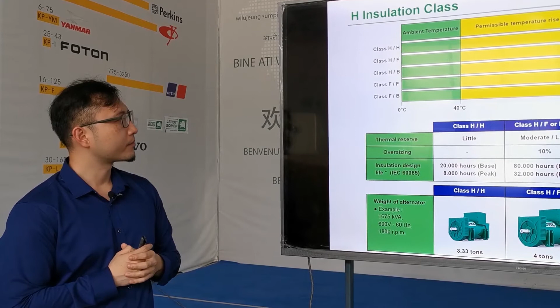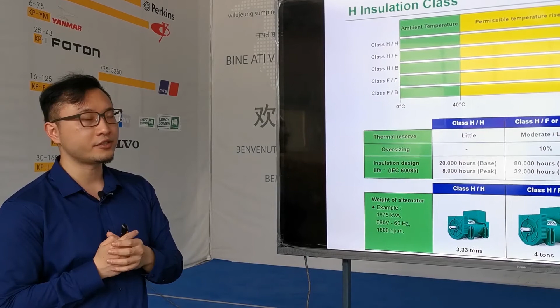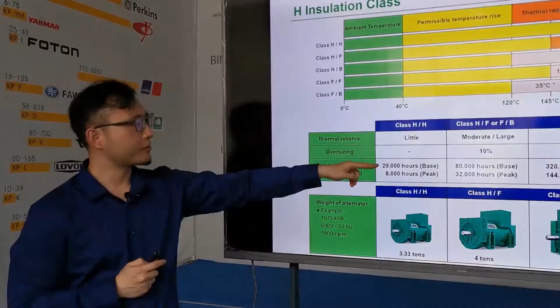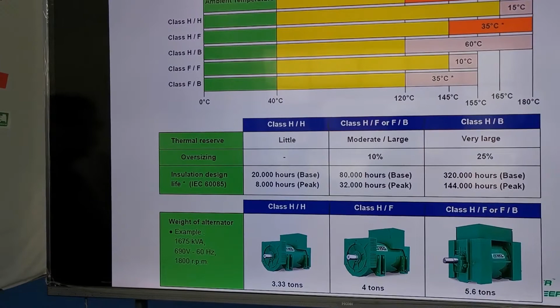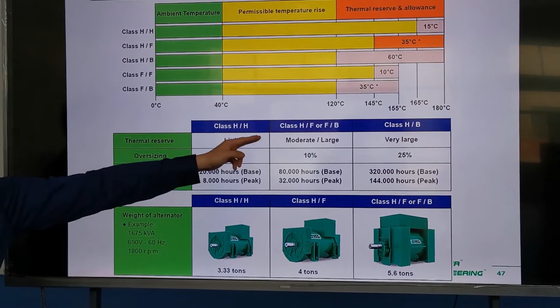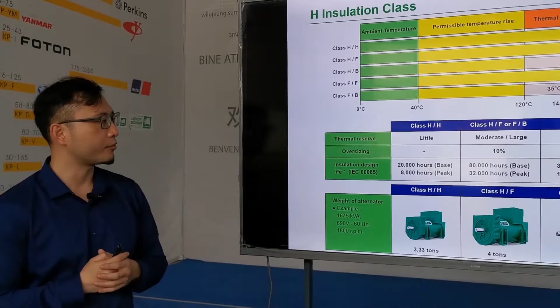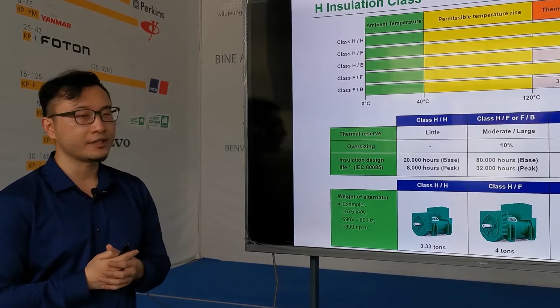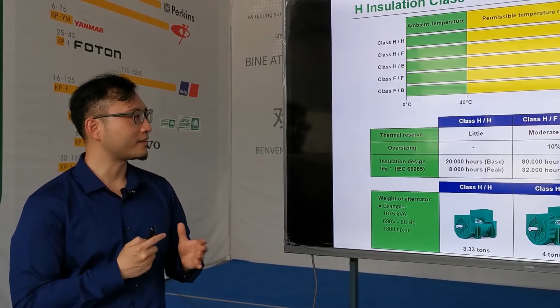There are two definitions here: one is insulation class, and one is temperature rise class. If the insulation class and temperature class are at the same level, the longevity of the insulation system will be about 20,000 hours. If the insulation class is one level higher than the temperature rise class, for example H/F or F/B, the life of the insulation system will be about 80,000 hours. And if two levels higher, for example H/B, the longevity could be about 320,000 hours. These numbers are all from third-party data.